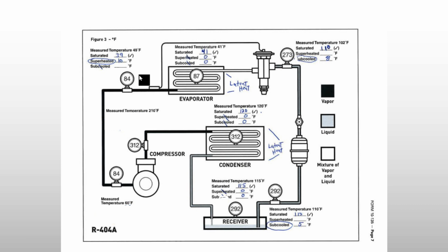We're going to leave it where it is, and we're going to follow the suction line down to where it goes into the compressor. So this would be, we measured TXV superheat. Now I want to know what total superheat is back to the compressor, which is important. It affects the cooling of the compressor. If it's a semi-hermetic type of compressor that draws refrigerant through the motor windings, it has to be set up for compression ratios, and so on. So we need to know what the total superheat to the compressor is.